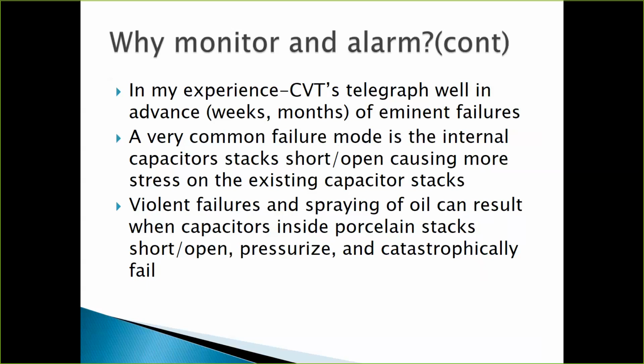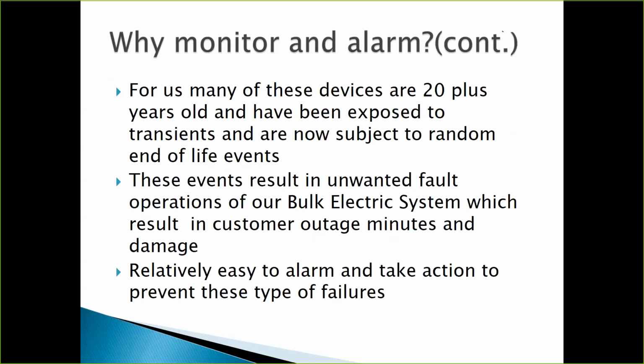And I guess the physics of the matter is it shorts, pressurizes that stack, and you saw how violent that failure was. You have electrical forces, you have pressure forces, you have gas forces from the oil expanding. So it's just a very, very hazardous condition. It's one we want to prevent. For us, in our industry, most of these devices are 20-plus years old. These are active devices. They're on the system constantly. They've been exposed to transients, and now they're near their end of life, okay?